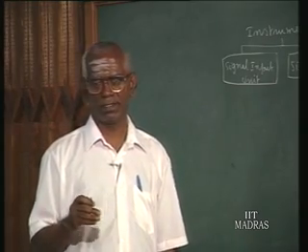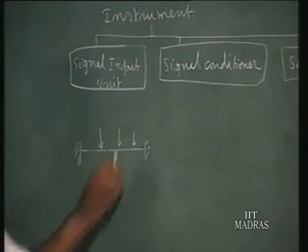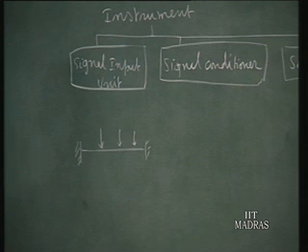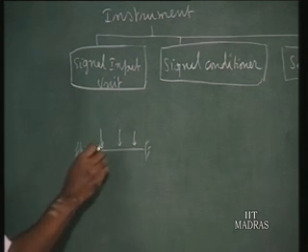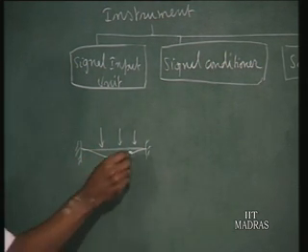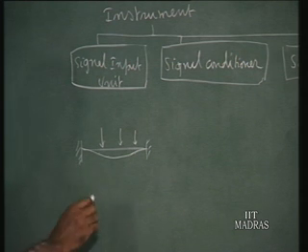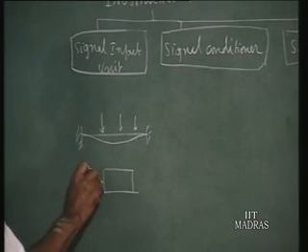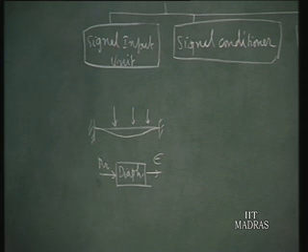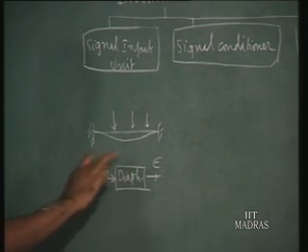For example, in pressure measurement, we have a diaphragm. The pressure acts over the diaphragm. That is our first transducer in pressure instruments. The diaphragm, on receiving a pressure on one side, deforms. Because of deformation, the diaphragm is subjected to strains at different locations. So what you achieved by this diaphragm is that pressure is transduced into a strain epsilon. By using the diaphragm, we have transduced the pressure into a strain signal. It is a transducer because one physical parameter is converted into another physical parameter.